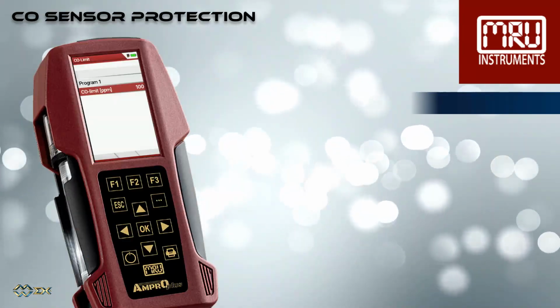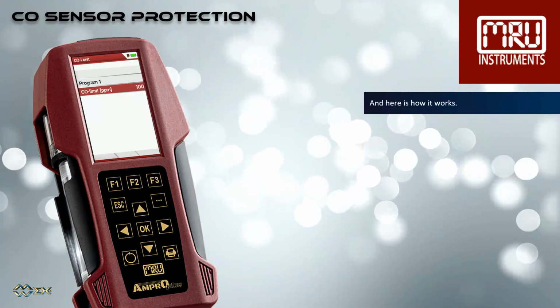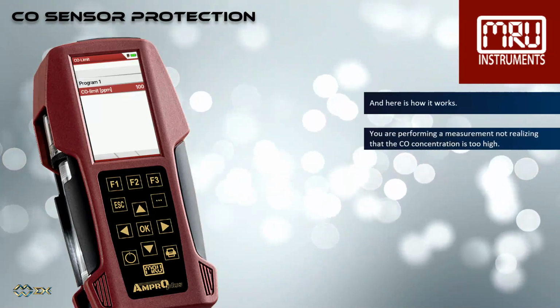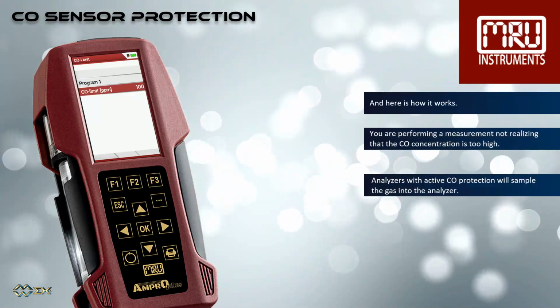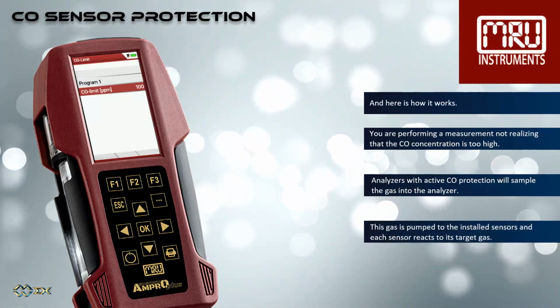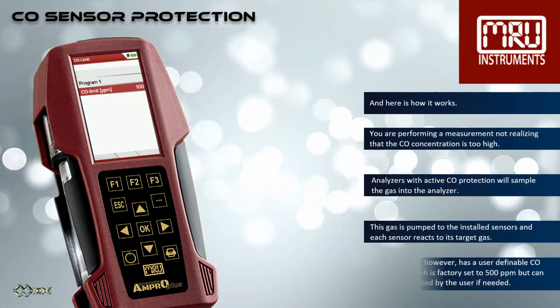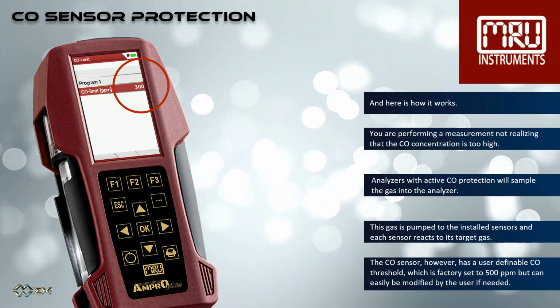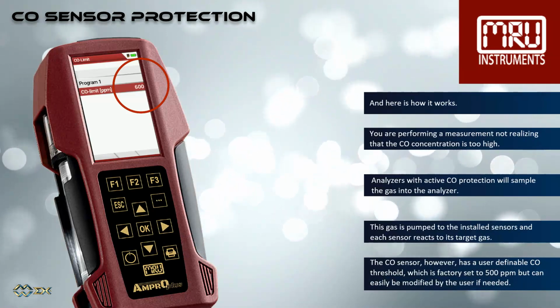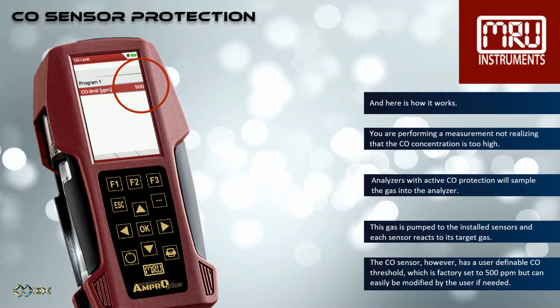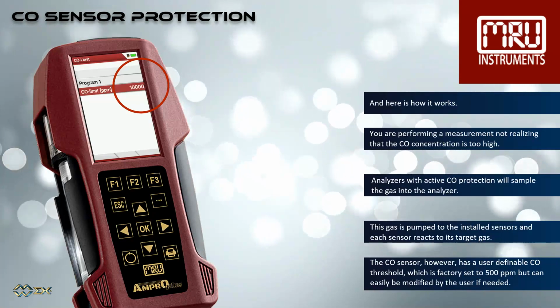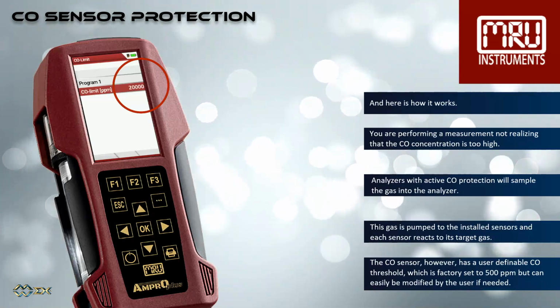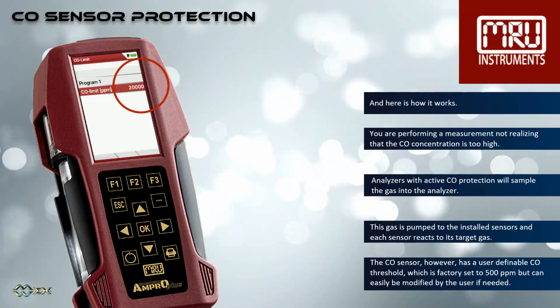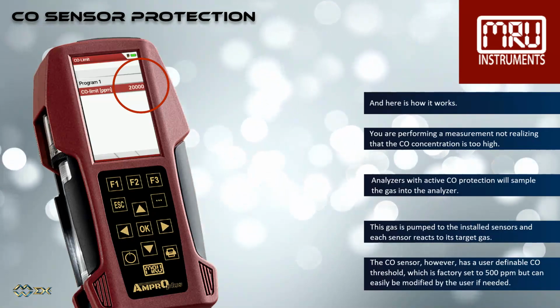And here is how it works. You are performing a measurement not realizing that the CO concentration is too high. Analyzers with active CO protection will sample the gas into the analyzer. This gas is pumped to the installed sensors and each sensor reacts to its target gas. The CO sensor, however, has a user-definable CO threshold, which is factory set to 500 ppm but can easily be modified by the user if needed.